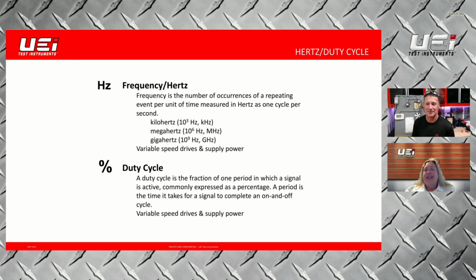Another important functionality is being able to read your frequency, your hertz, and your duty cycle. This is becoming a lot more important as we move into three-phase motors, so why not buy a meter that already has these functions? Frequency is the number of occurrences repeating, and duty cycle is the fraction of the period during which a signal is active. You'll find those values a lot in manufacturer specs. Manufacturers put in fail-safes and control boards that tell you the faults, but it's always good to be able to double check those yourself.